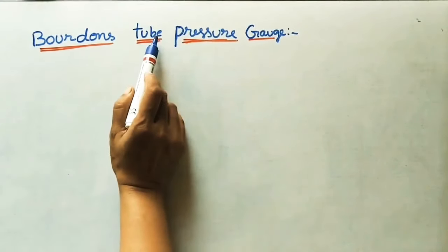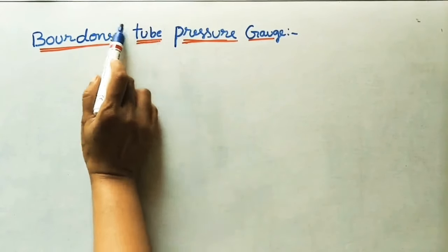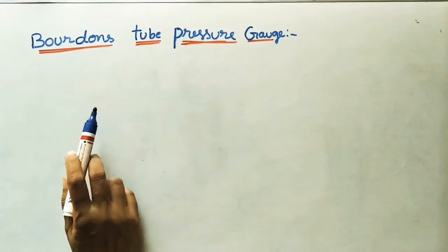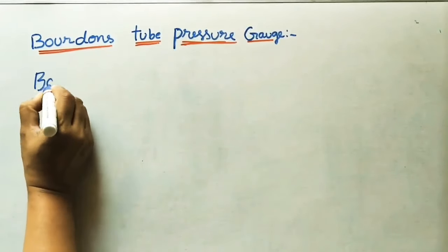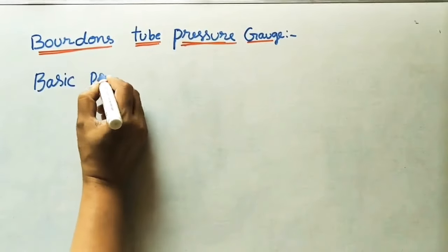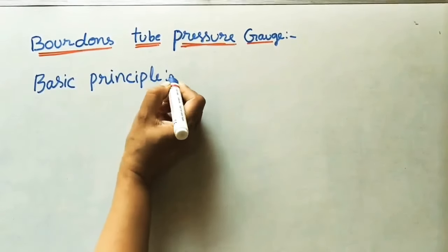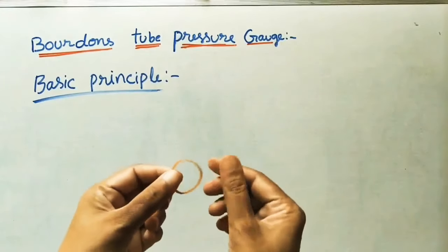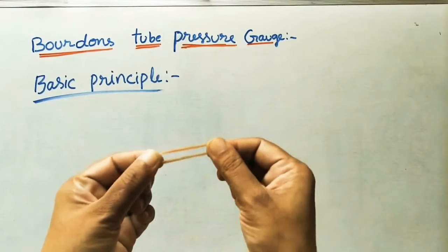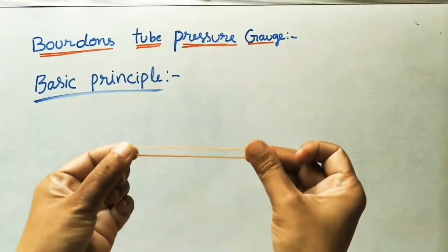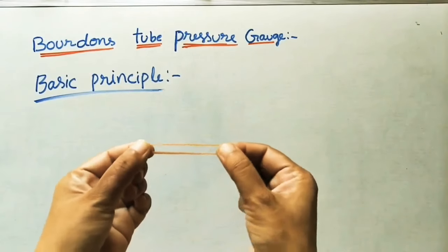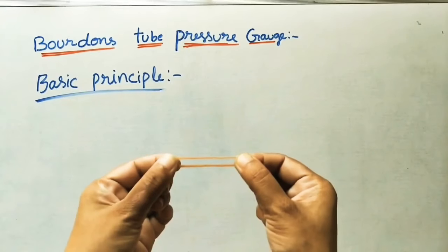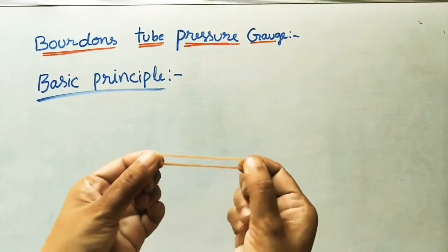In the Bourdon tube pressure gauge, one elastic tube is used — that is why it is called the Bourdon tube pressure gauge. On what principle does it work? The Bourdon tube has an elastic property. For example, when force is applied to a rubber material, because of elasticity it will elongate or deflect. If more pressure is applied, the deflection is more; if less pressure is applied, the deflection is less.